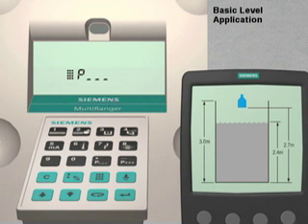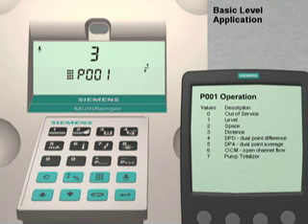We then enter 001 for parameter number 1. Parameter 1 sets the type of measurement for the application. As you can see, it is currently set at 3, which is the factory default value. With this value, the multi-ranger would measure the distance from the transducer to the liquid surface.